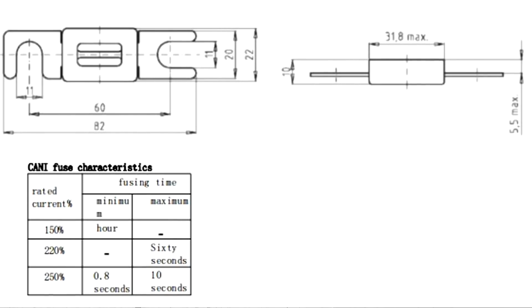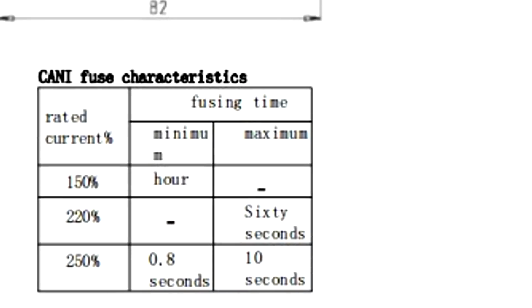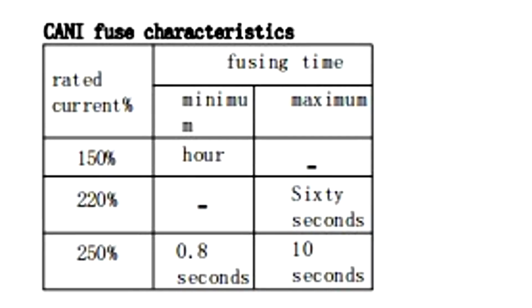So the fuse characteristic down here is: rated current 150% of the rated current for 1 hour, 220% for 60 seconds, and 250% for 0.8 to 10 seconds. So that's a very interesting characteristic of this fuse.